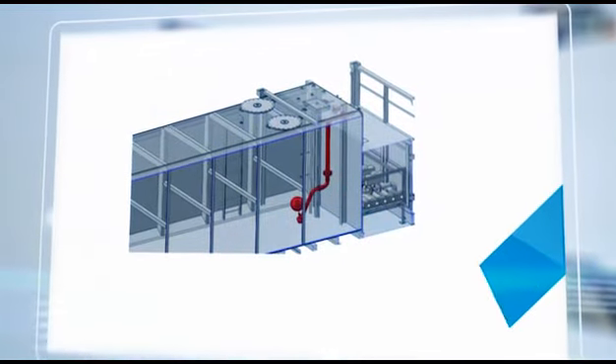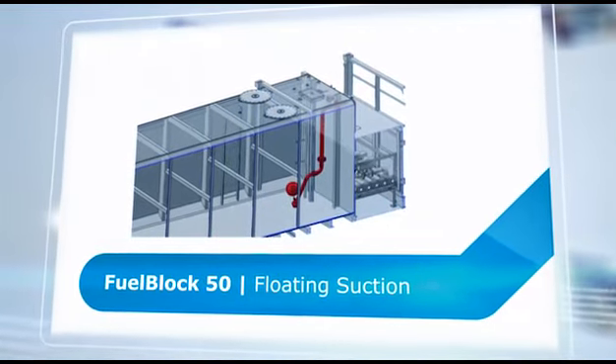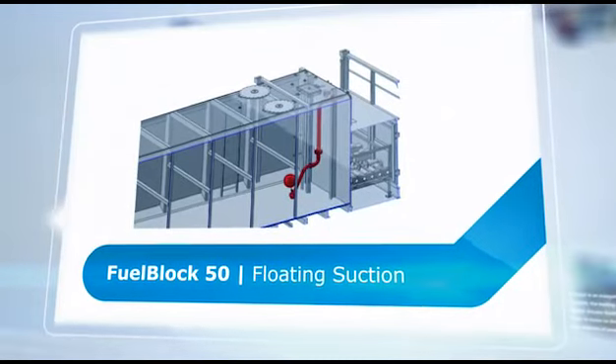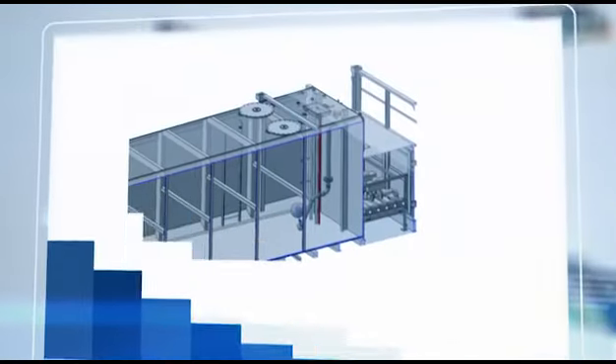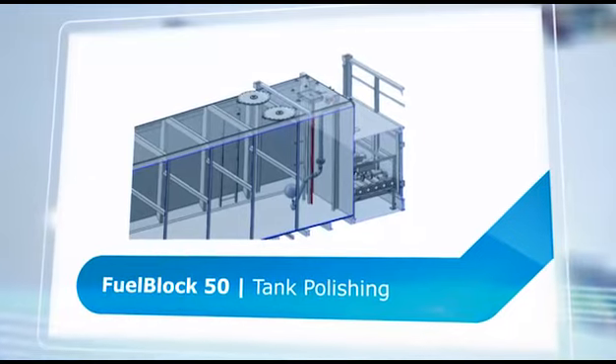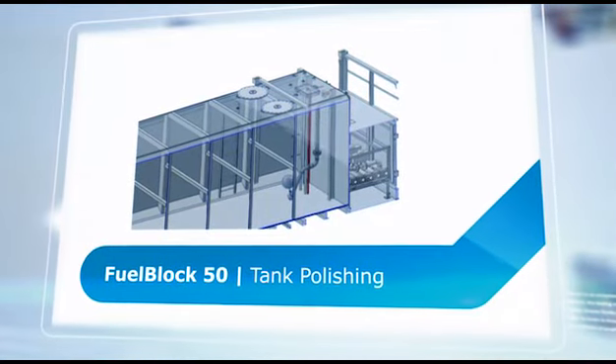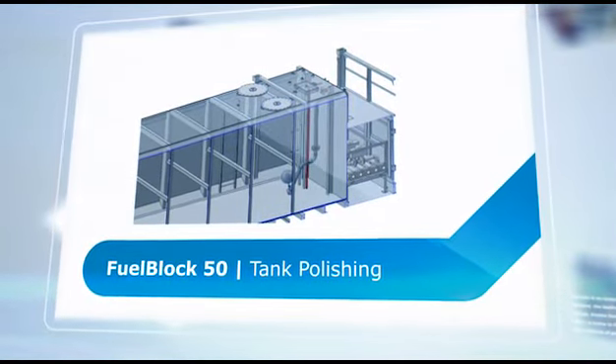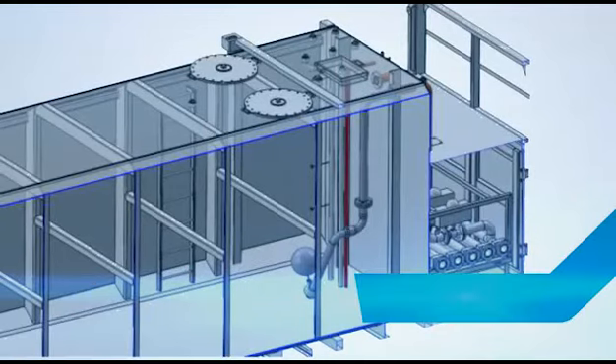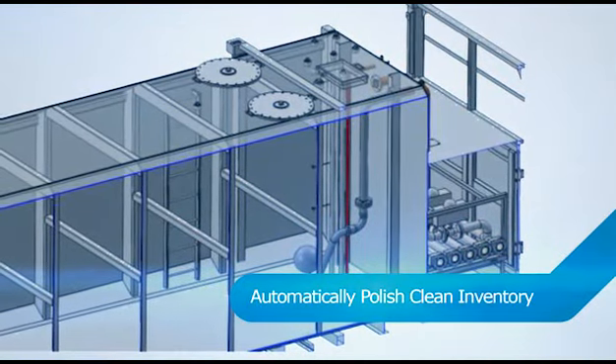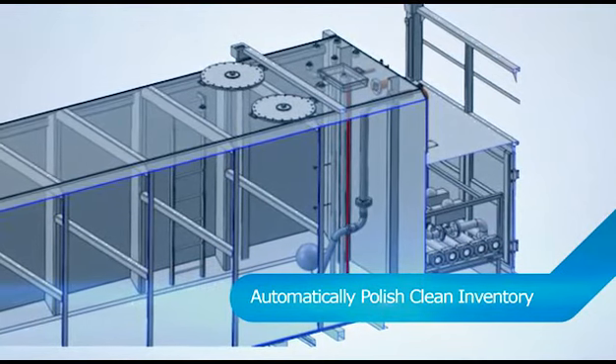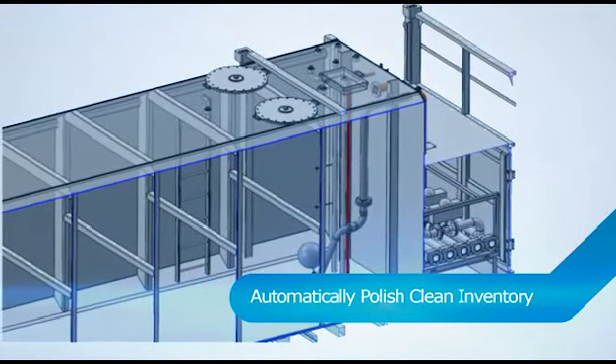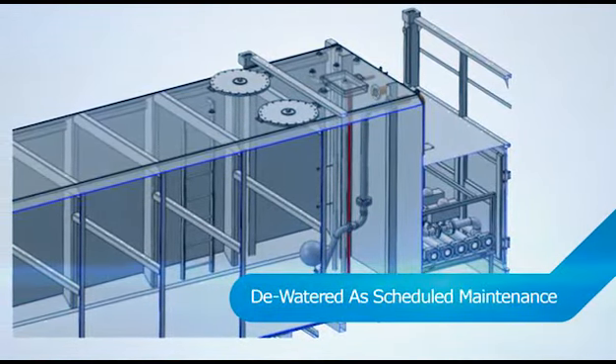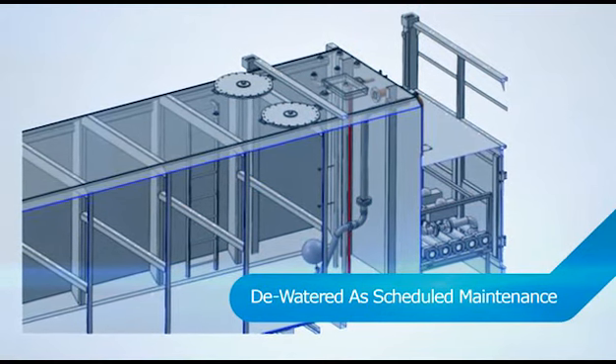A floating suction line ensures the pump suction is suspended in the upper fuel inventory. An internal drain line is included with each tank. The drain line draws from the bottom of the tank where any water or particulate matter will settle. Clean fuel tanks may be configured to automatically polish the clean inventory by processing with the centrifuges. Raw tanks are typically de-watered as a scheduled maintenance activity.